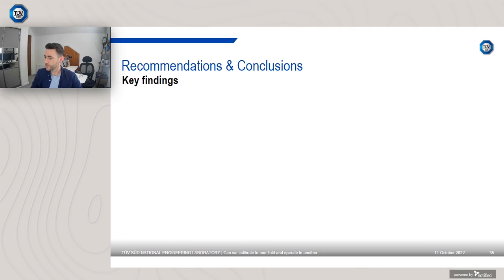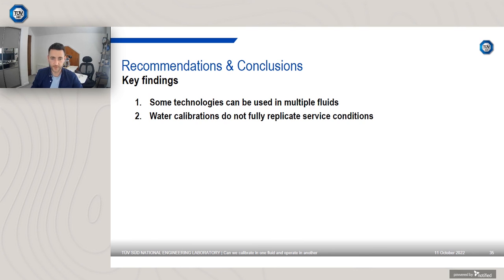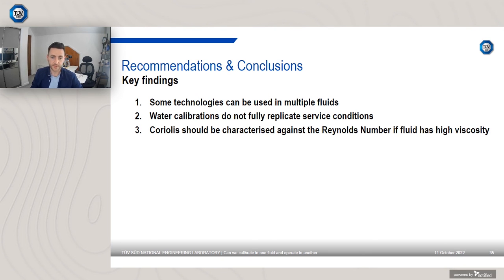So just checking the time just now. So 15 minutes remaining, so almost finished. Just at the recommendations and conclusions. So some technologies can be used in multiple fluids, but not all. So straight away, you can't use all flow meters with different fluids. Water calibrations do not fully replicate service conditions, certainly with respect to temperature and pressure. Coriolis meters should be characterised against Reynolds number if the fluid is high viscosity. I've already shown you that high viscosity clearly affects the performance of Coriolis meters.